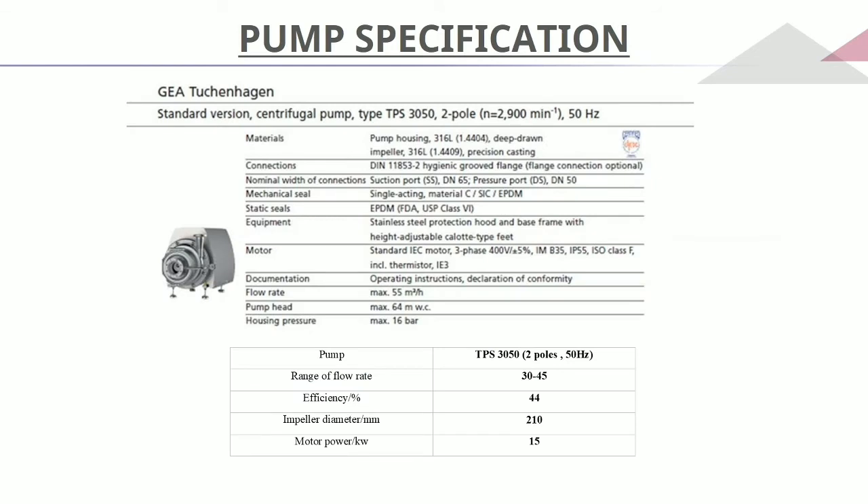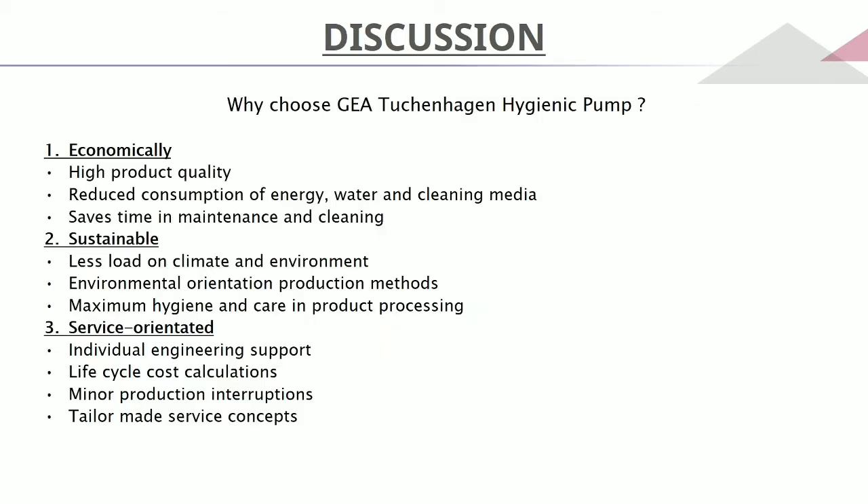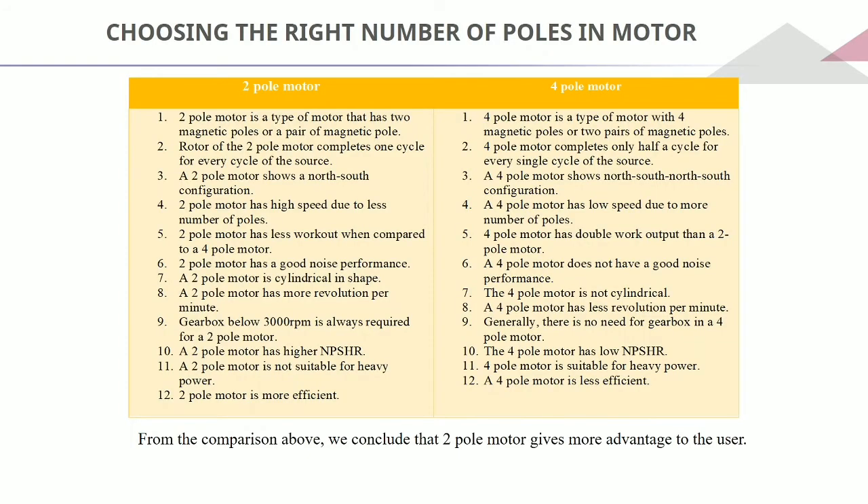For the centrifugal pump overall description, we have chosen a higher motor power of 15 kilowatts compared to the 12.5 kilowatts required, for safety purposes. We chose the GEA Tuchenhagen pump because it is economical, sustainable, and service-oriented. We chose a two-pole motor over a four-pole motor because it has better noise performance, higher NPSH required, and is more efficient. We conclude that the two-pole motor gives more advantage to the user.